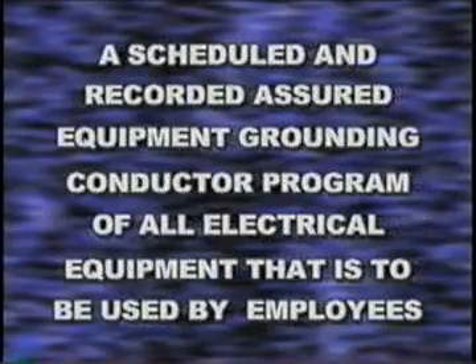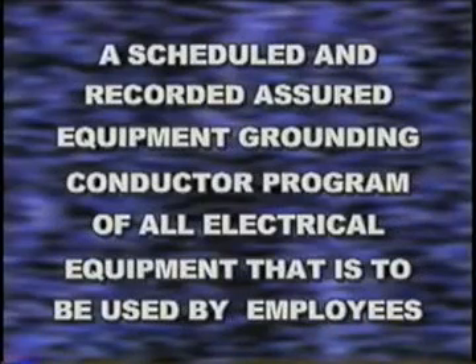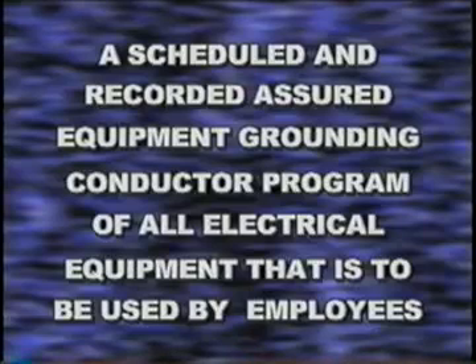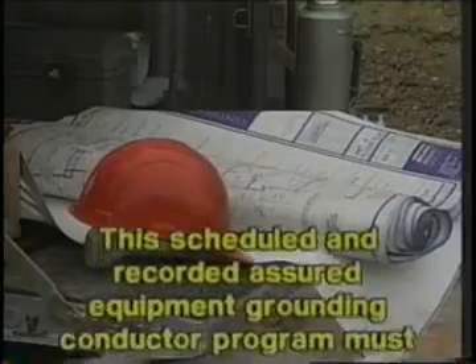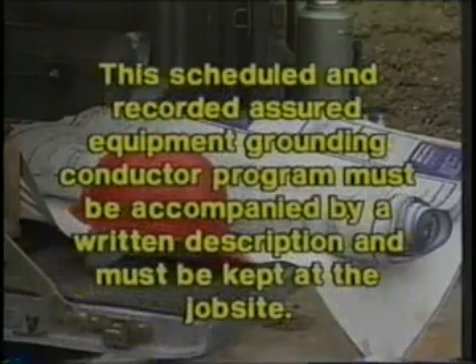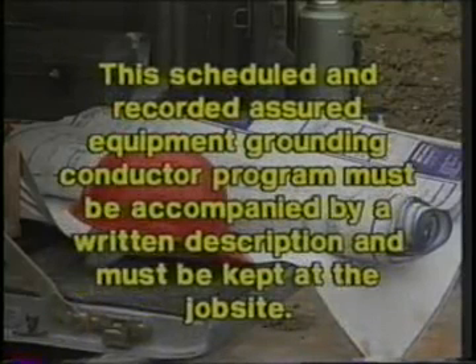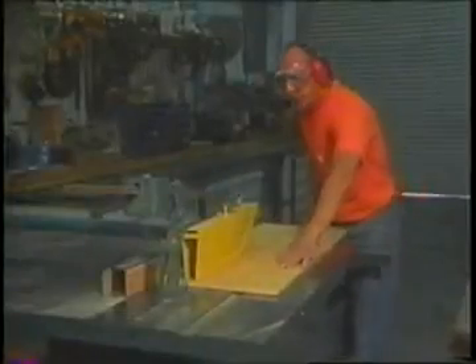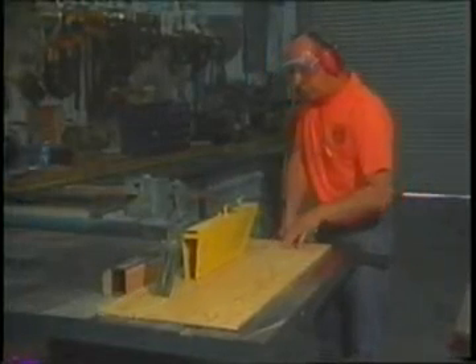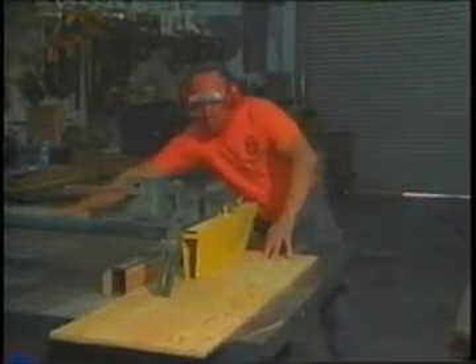or a scheduled and recorded assured equipment grounding conductor program covering all cord sets, receptacles which are not a part of the permanent wiring of the building or structure, and equipment connected by cord and plug which are available for use or used by employees. This schedule and recorded assured equipment grounding conductor program must be accompanied by a written description of the program, including the specific procedures adopted, and it must be kept at the job site. This program should outline the employer's specific procedures for the required inspections, tests, and test schedule.